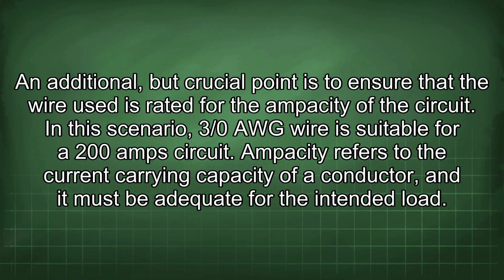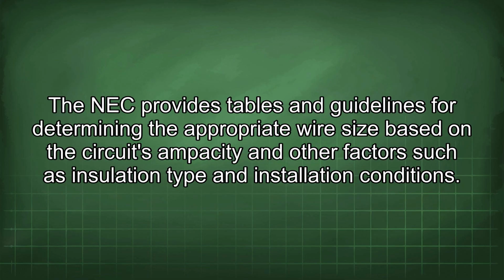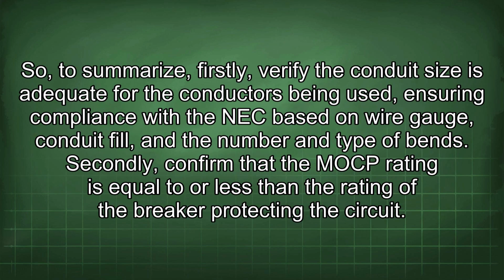Ampacity refers to the current carrying capacity of a conductor, and it must be adequate for the intended load. The NEC provides tables and guidelines for determining the appropriate wire size based on the circuit's ampacity and other factors such as insulation type and installation conditions. So, to summarize, firstly, verify the conduit size is adequate for the conductors being used, ensuring compliance with the NEC based on wire gauge, conduit fill, and the number and type of bends.